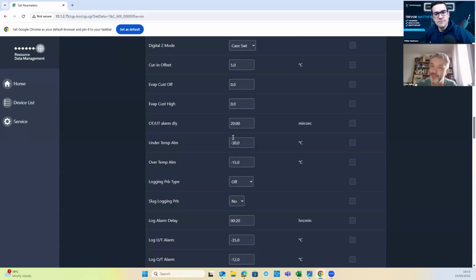Set them sensibly. Customers, if they see a temperature alarm all the time, are going to ignore it, because that's what customers do. They need to only see that alarm when it's serious, right? I don't know who uses an under temperature alarm on freezers these days. Under temperature alarm on chillers for when your valve's stuck, definitely. And over temperature alarm for everything. Set it realistically. Customers are going to have a spec.